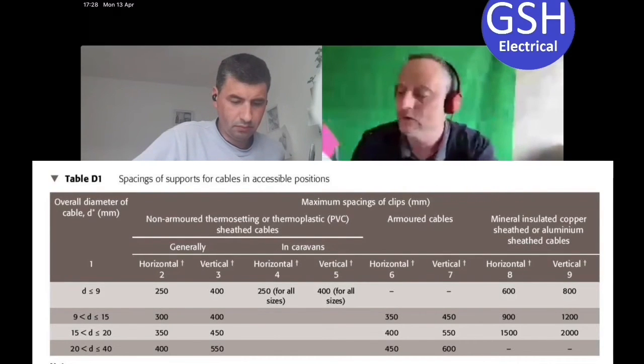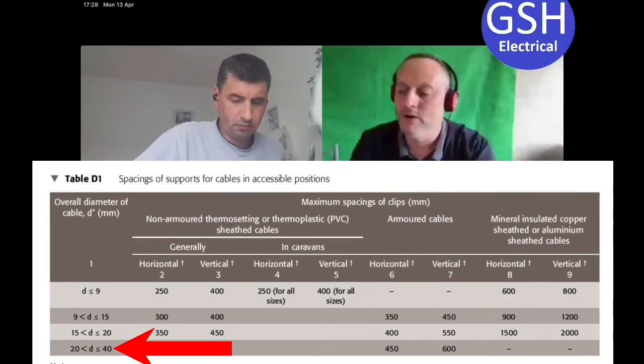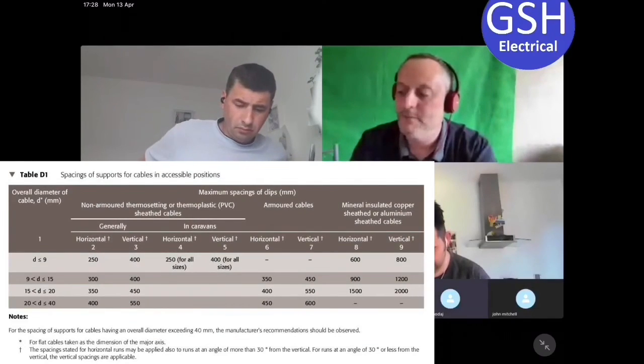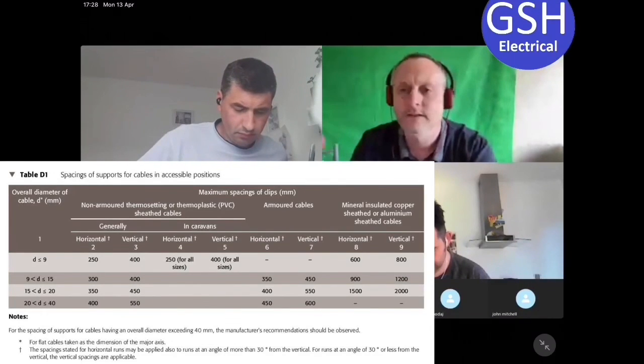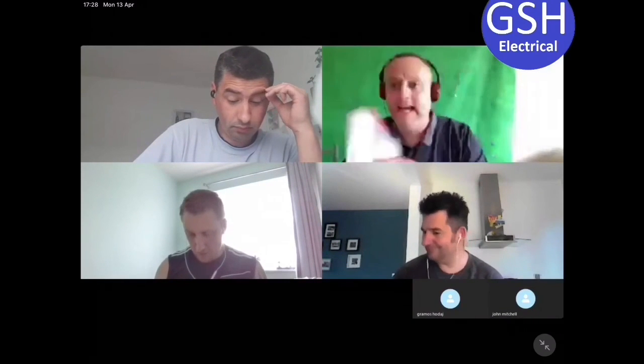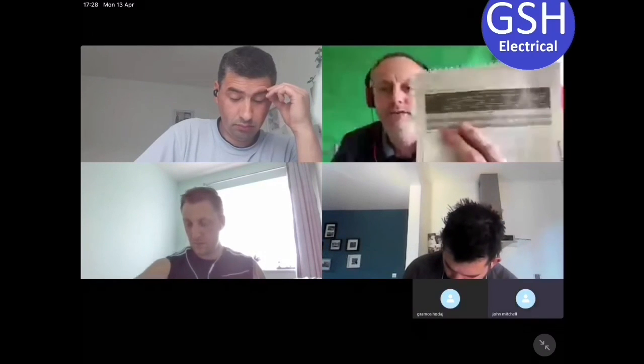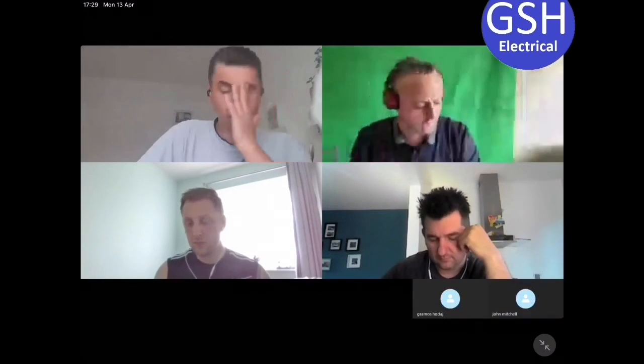The table only goes up to 40mm diameter. There is a footnote at the bottom of the page saying cables with diameters greater than 40mm should follow the manufacturer's instructions. This is a page worth familiarizing yourself with. If someone from NICEIC or NAPIT comes to do your domestic installer inspection and asks the maximum clipping distance for your cable, you should be able to flip it open, measure the diameter, and give them the answer.